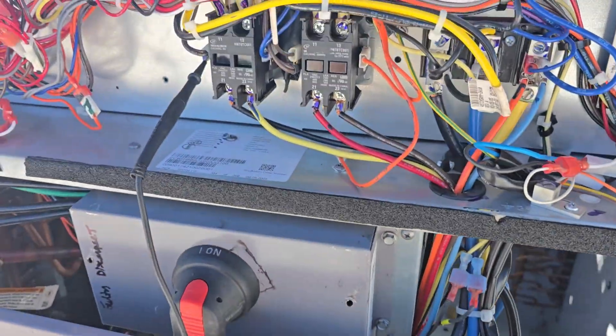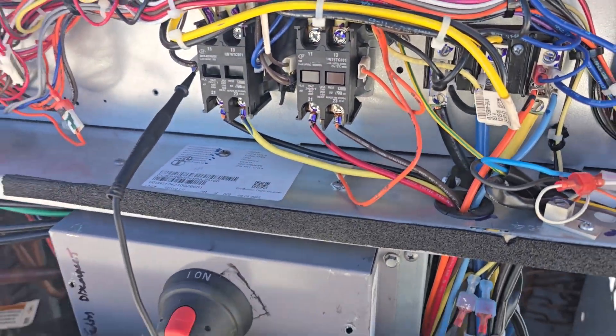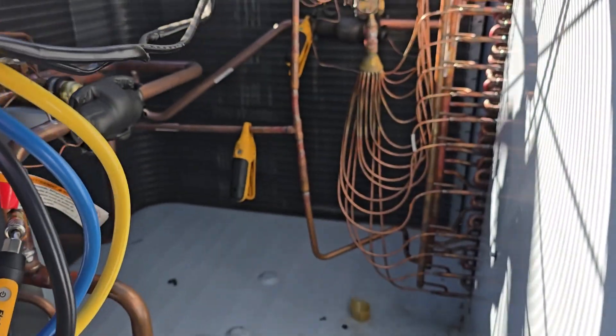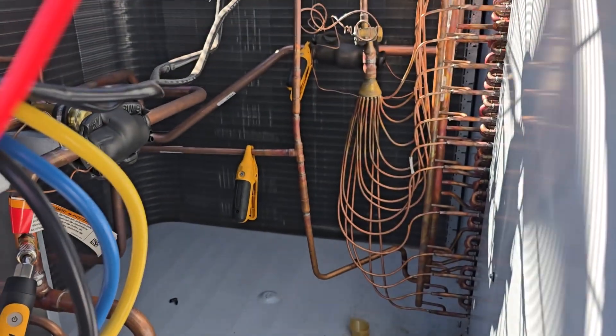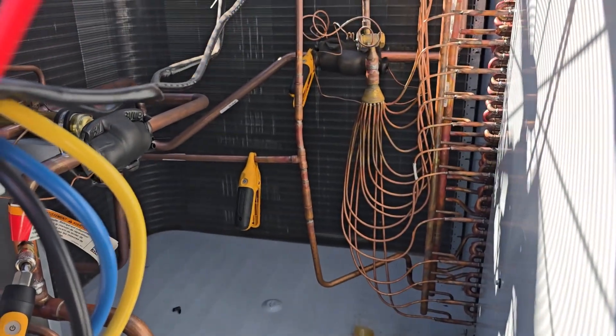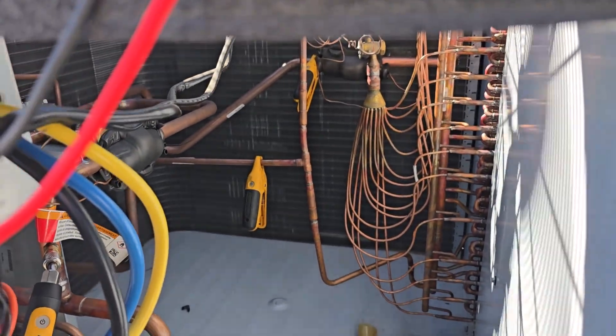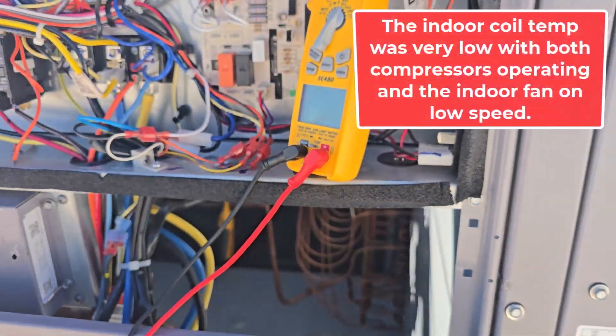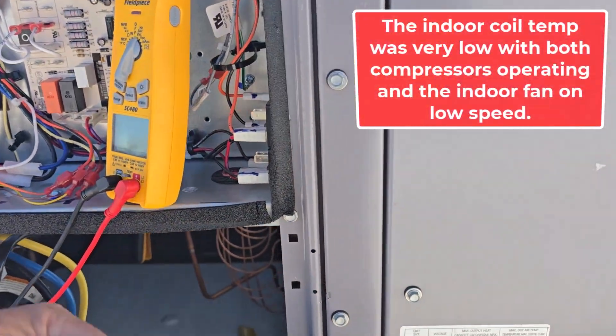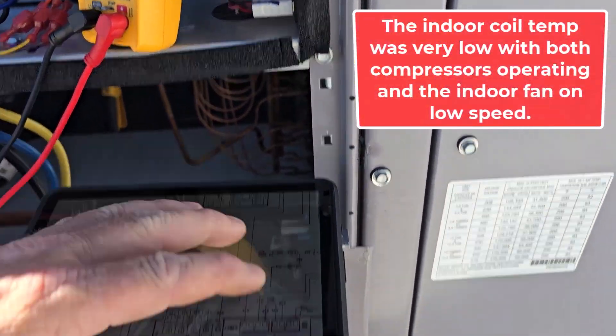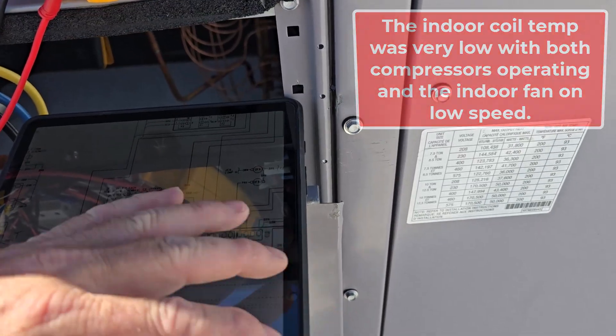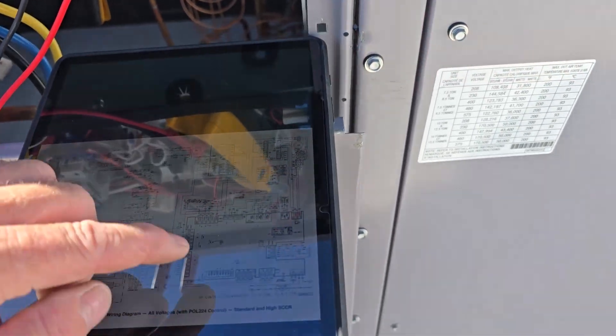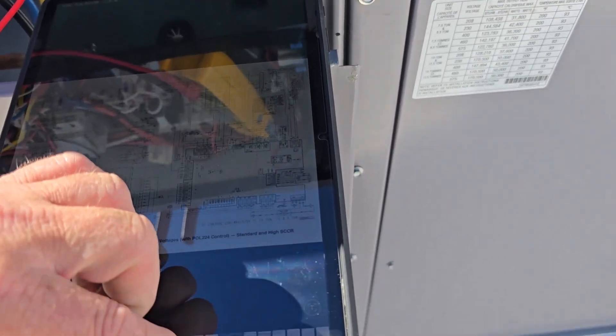So with it unplugged and on Y1 only, pressures were all returned to normal. No longer had like 30 to 35 degree split temperature. Everything's good, see here.